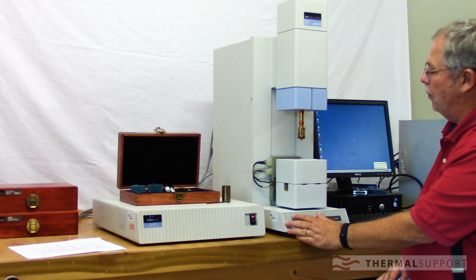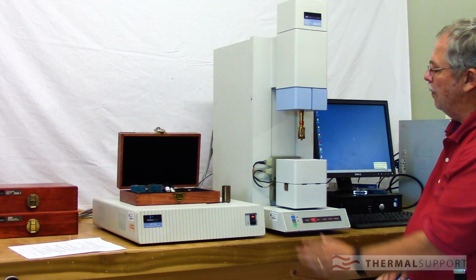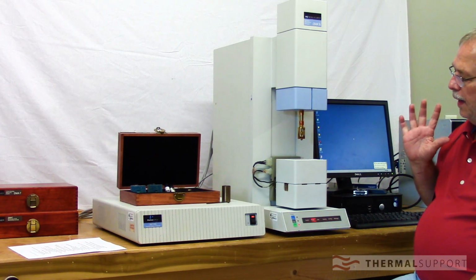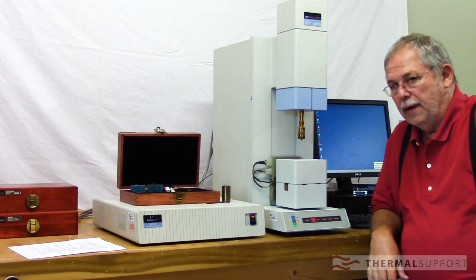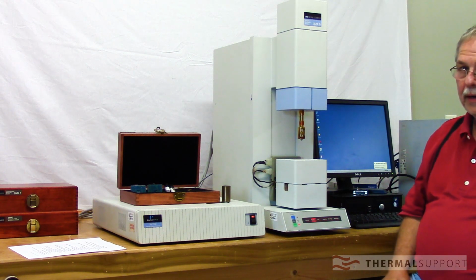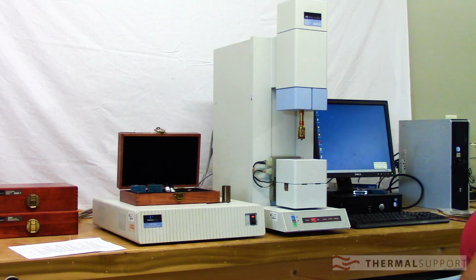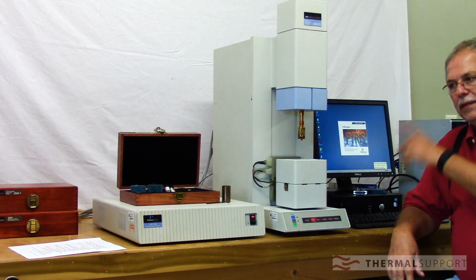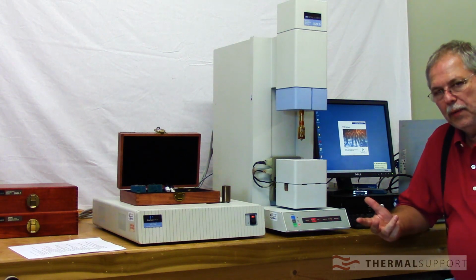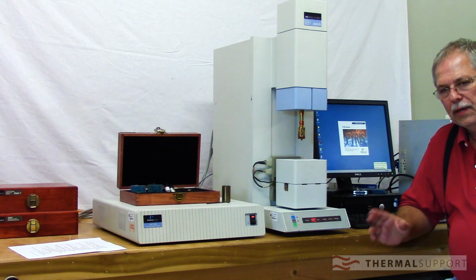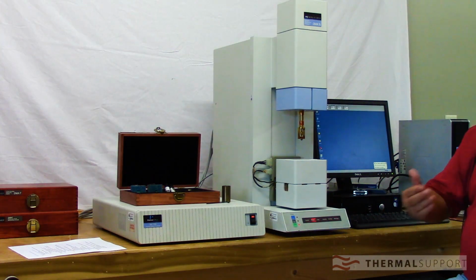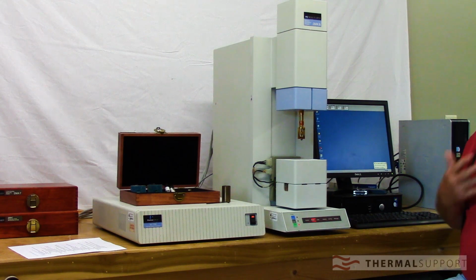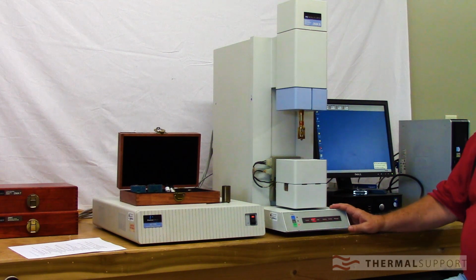And at this point in time, if you wanted to tell it to go up, it would go up. Now there's one critical thing you have to remember right now. This instrument is not ready to go. What needs to happen is you need to open up your Pyris software. The very early versions of these analyzers had two EEPROMs in there. You can identify them because they're 8005, 8006. PerkinElmer really wanted to make sure that it was as rock solid as they could, so they went to 8007, 8008.